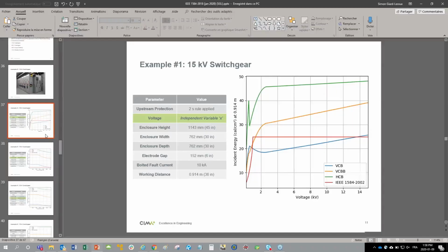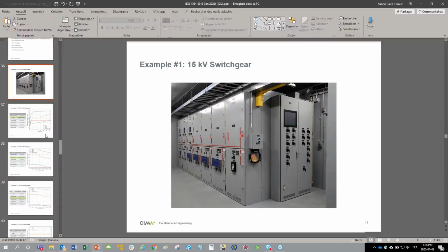All right. This is from Jeremy. He says, don't most of the changes allow for a lower cal rating? In most cases, isn't EasyPower's default settings the most conservative? From a company liability aspect and personal safety, why would we not just use the most conservative values? Example, the default results in 13 calorie, and by changing the electrode configuration, it results in lower than 12 calories. Why would we not just use the 13 calorie value?